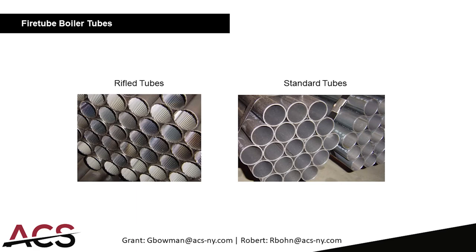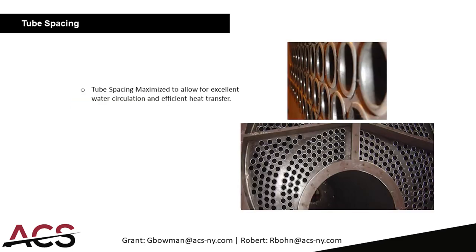There are different types of tubes. A standard tube is typically 0.105 inches in thickness. On the left are rifled tubes or XID tubes, which give more surface area and create more turbulence when the flue gases go through them, helping efficiency. Here is a picture of an assembled boiler tube sheet with nice, even spacing between the tubes, allowing for good water circulation between the tubes to receive even heat transfer to the water, which is very important for efficiency.